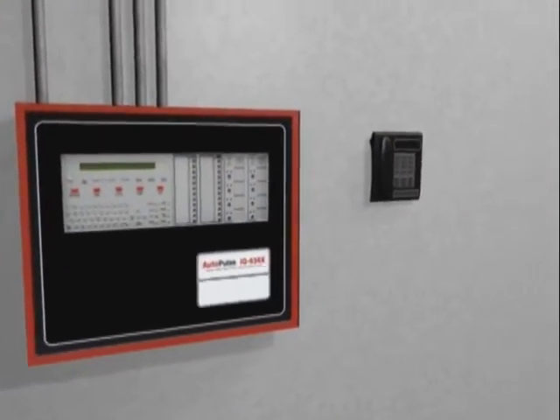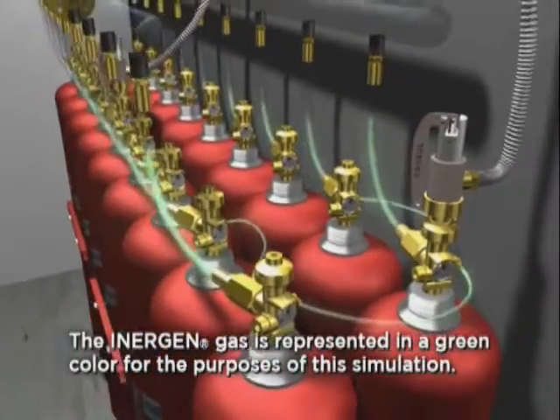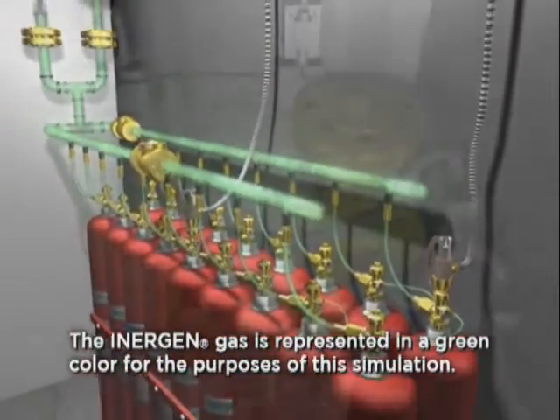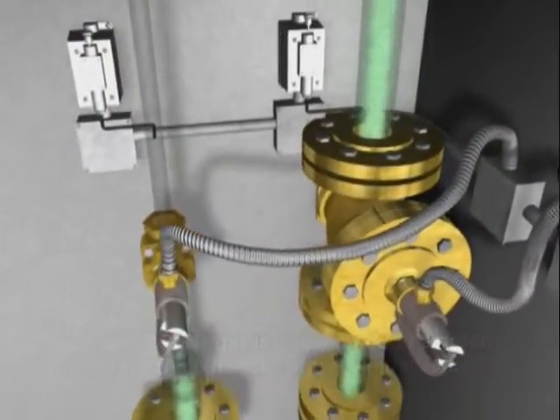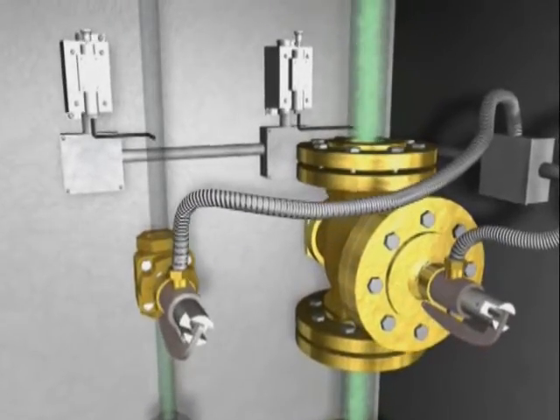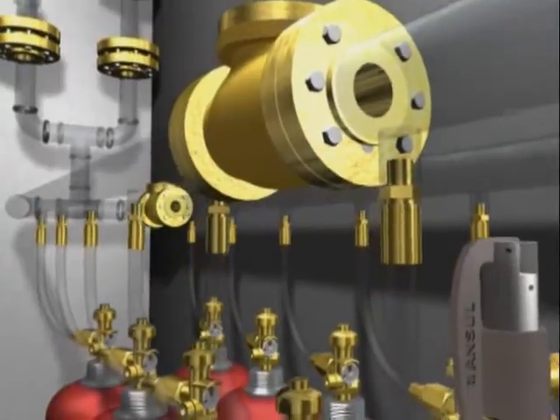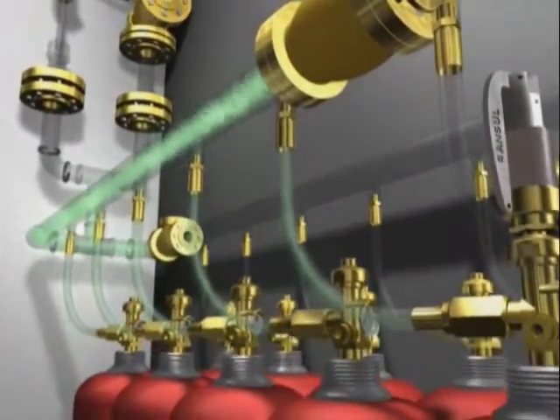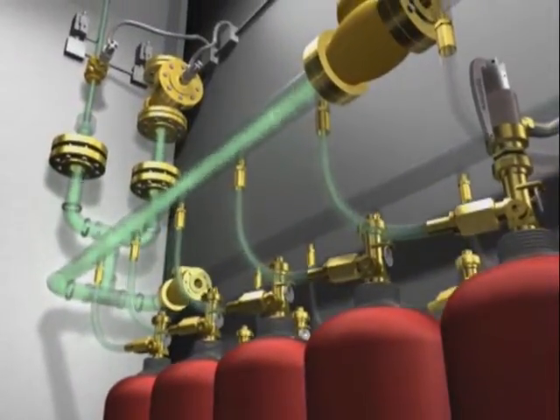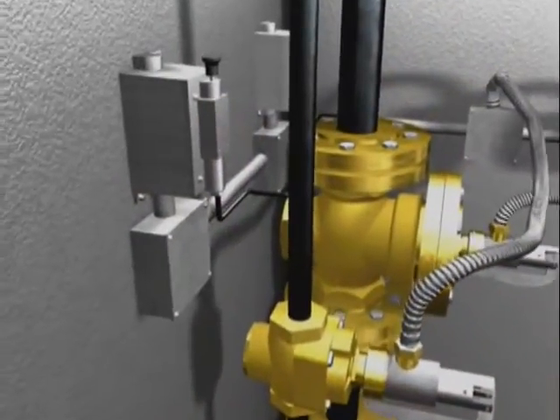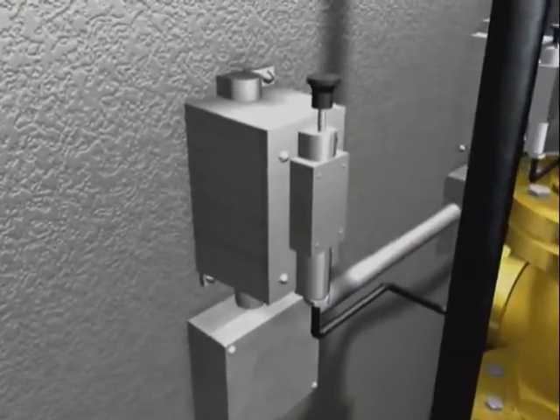After the prescribed time-delayed period, the autopulse control unit energizes the electric actuator on the Inergen cylinder valve. The cylinder valve opens, allowing the Inergen agent to discharge from the storage cylinders. In places where Inergen is protecting more than one room, a unique selector valve is used to direct the system discharge into the appropriate zone. A check valve is used in a selector valve system to separate the discharge of one zone from the other zone by preventing the Inergen flow to the main system cylinders. Simultaneously, one or more pressure switches can be actuated to pneumatically operate electrical circuits to close doors, trigger alarms, and turn on or off equipment. The Inergen agent is then distributed throughout the piping network.